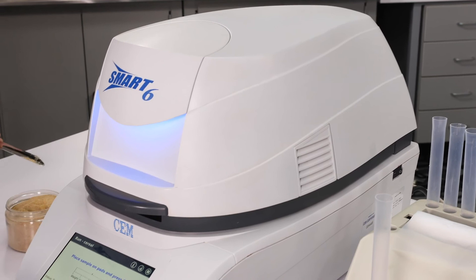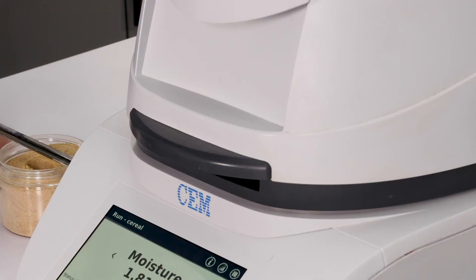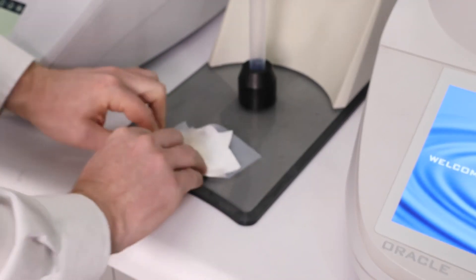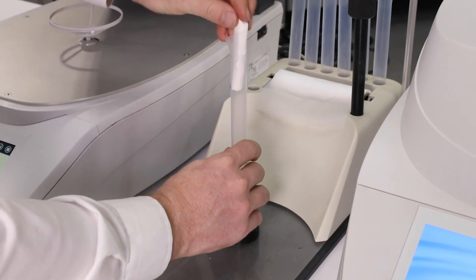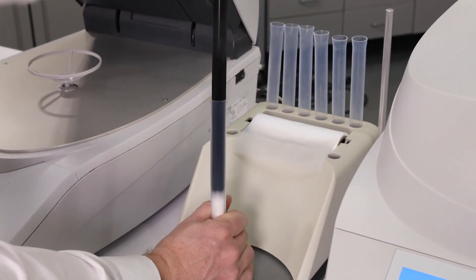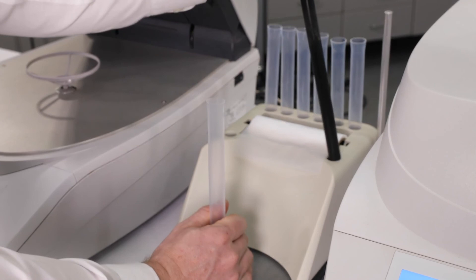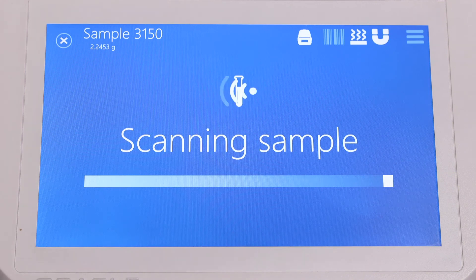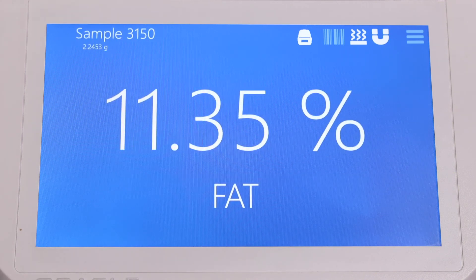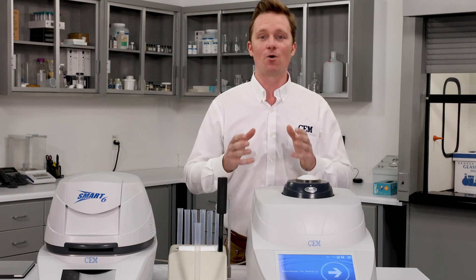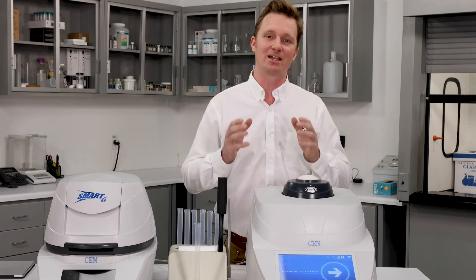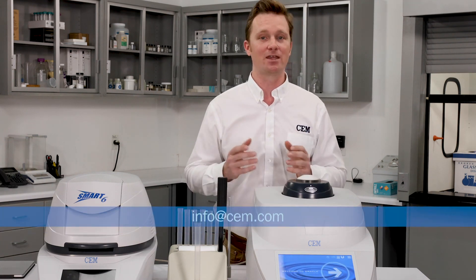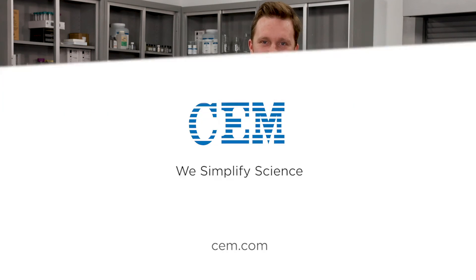Select a drying method and press start. Once the sample is dry, you will be prompted to place the sample in an NMR tube and into the Oracle. After a 30-second scan, results will be displayed. If you'd like more information or would like to see your samples run on the Oracle in a live virtual demo, reach out to your local sales representative or send us an email at info@cem.com. Thanks for watching.